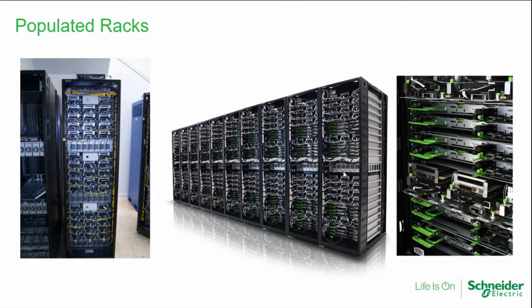In the one on the left there are two power shelves, and in the one in the middle there's one power shelf. The power supplies have been pulled out of the servers and are now centralized within the rack, which allows you to right-size. The power is distributed within the rack via DC bus bar — either 12 or 48 volts. We did some analysis showing how much oversizing you eliminate when you consolidate the power supplies, and it was a bigger savings than we expected.